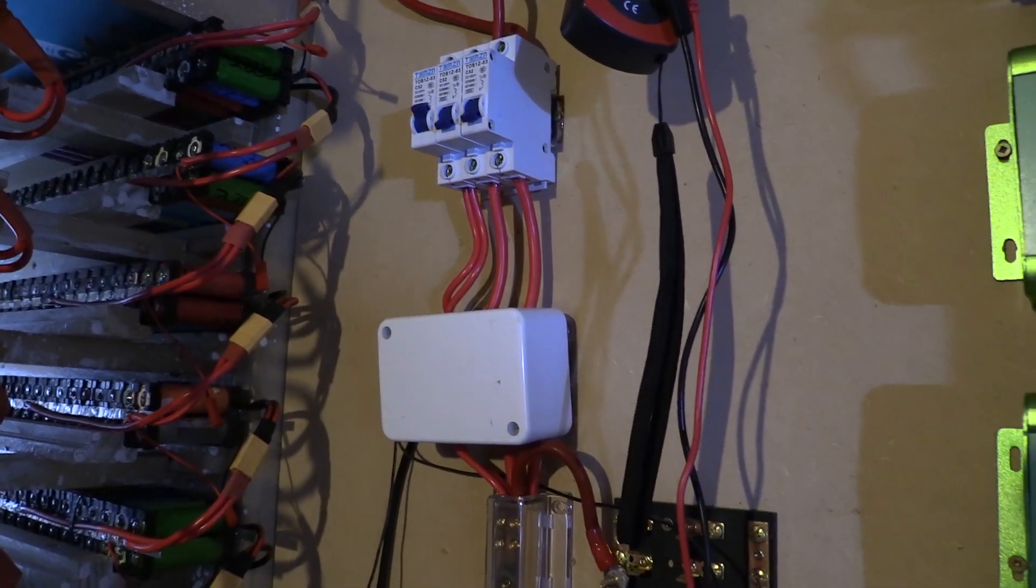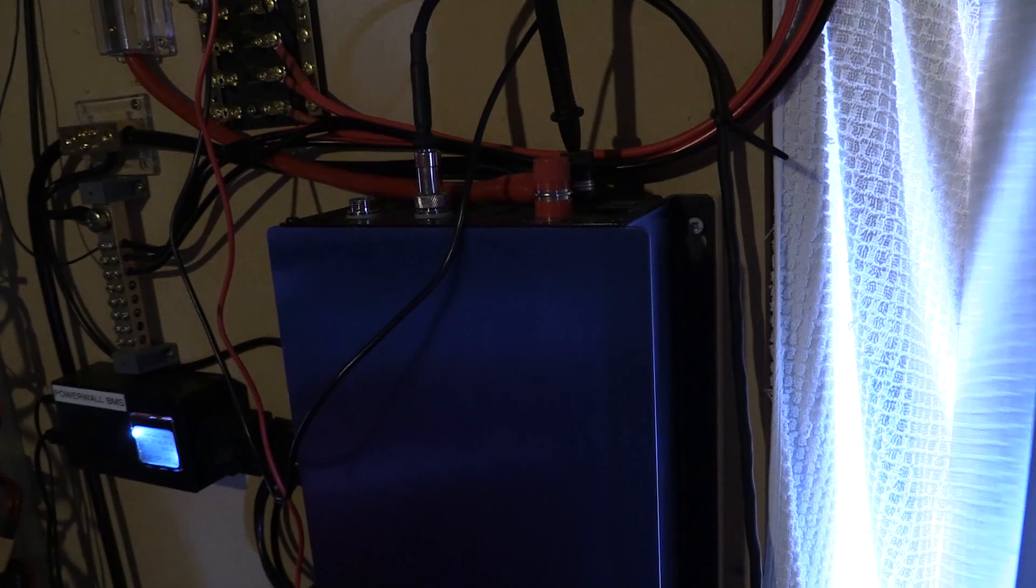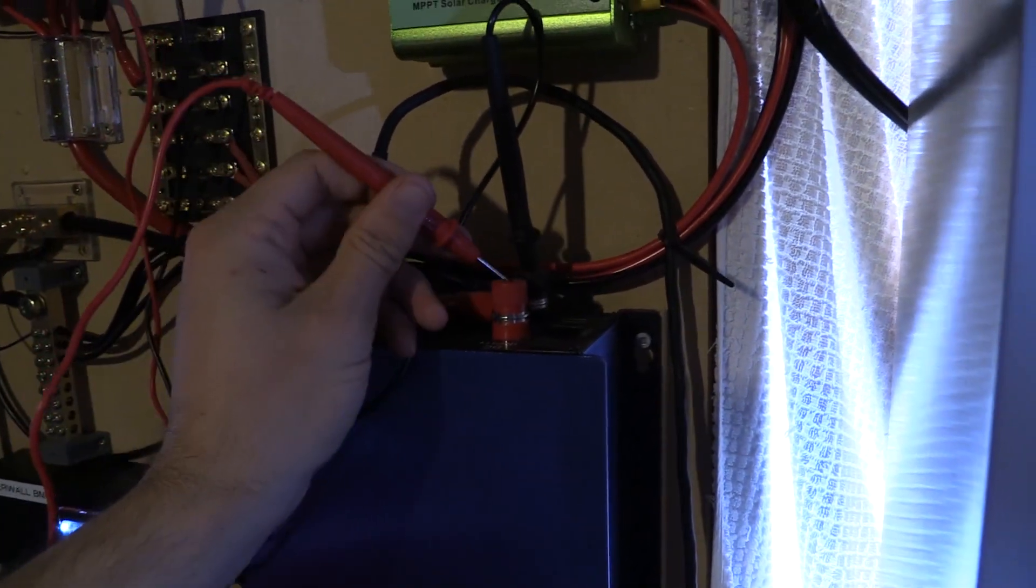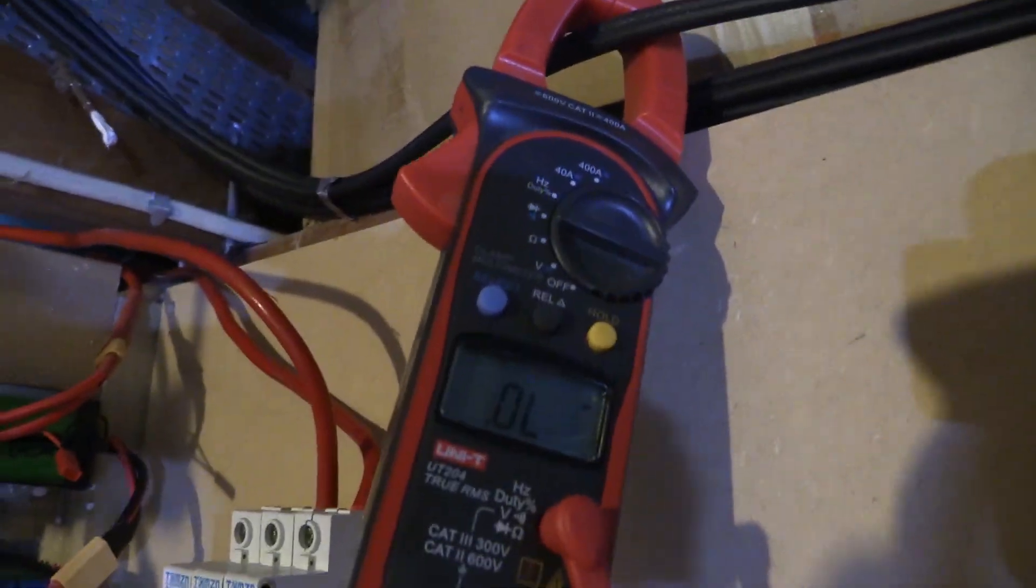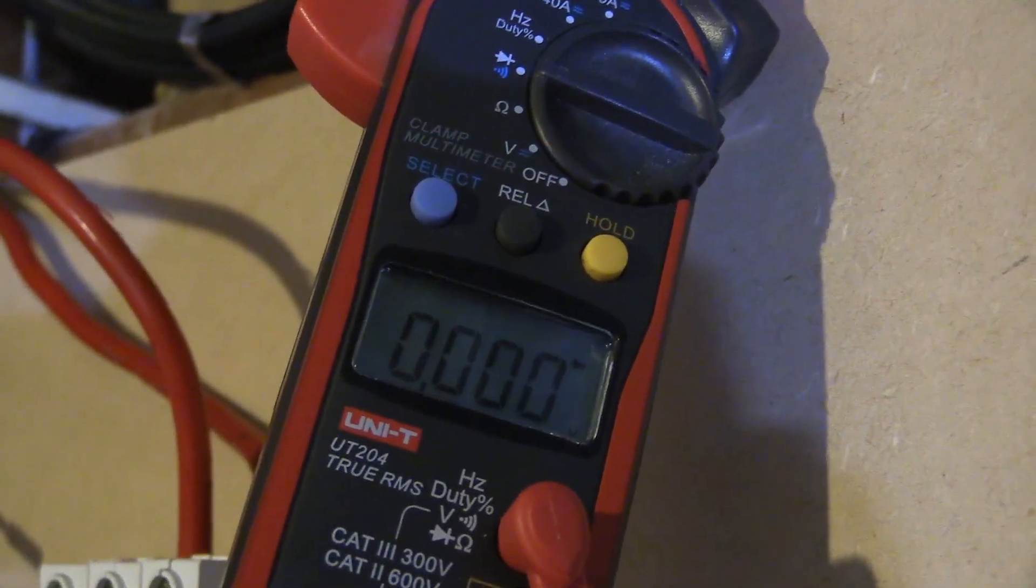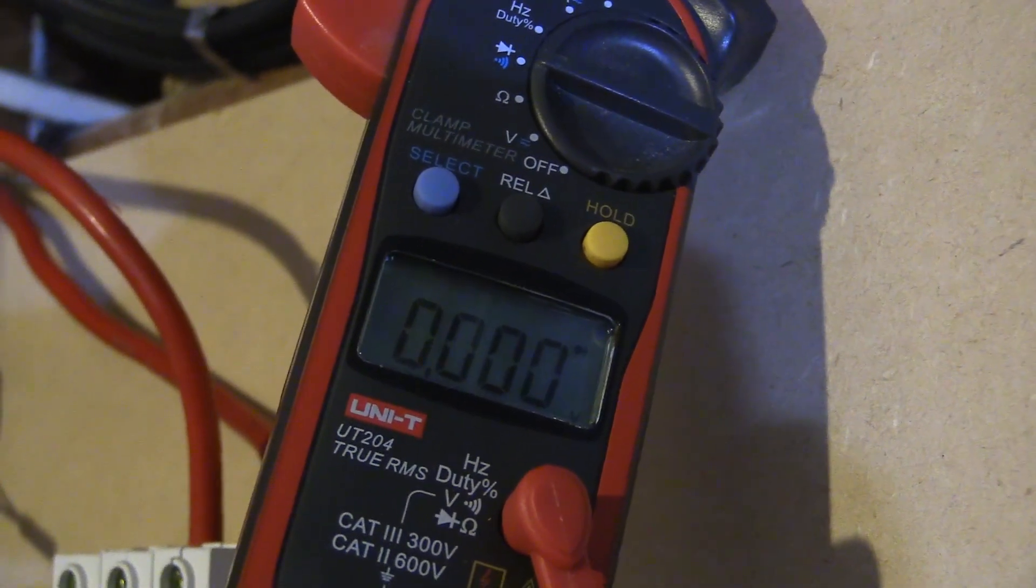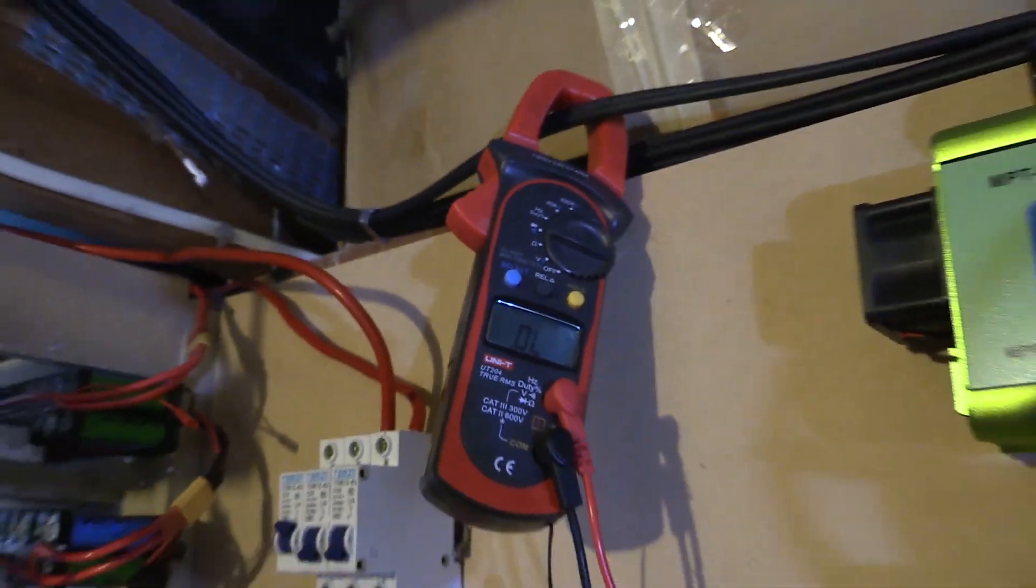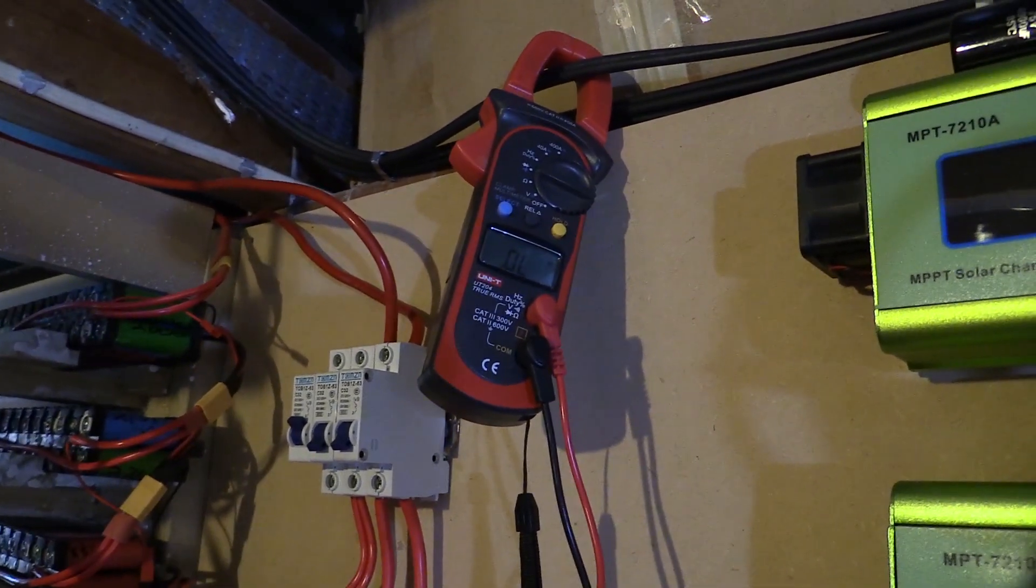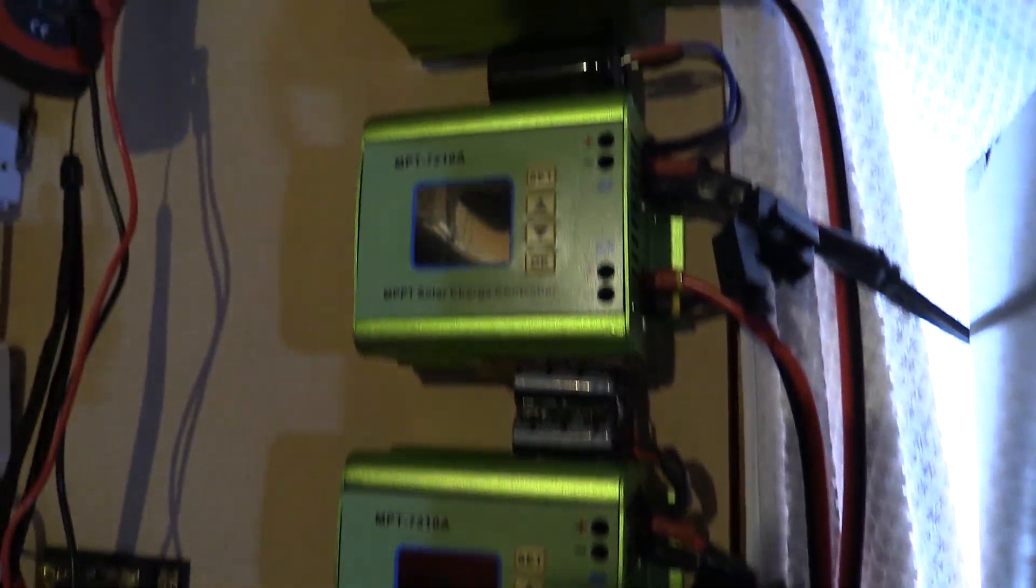So the thing that's died is the grid tie inverter. If I just double check across the poles here, wish this screen was better, it's a dead short on the DC side. It can't be anything else but that. I wonder if that's killed all these at the same time because they're all connected.